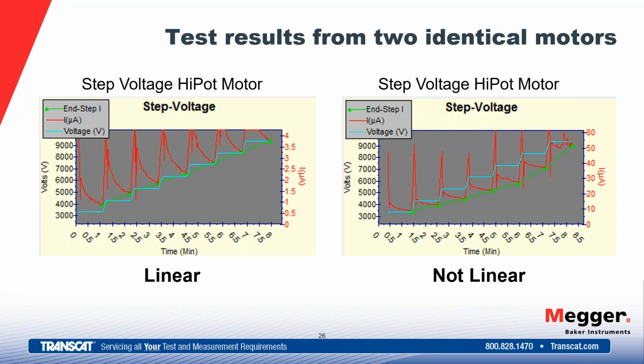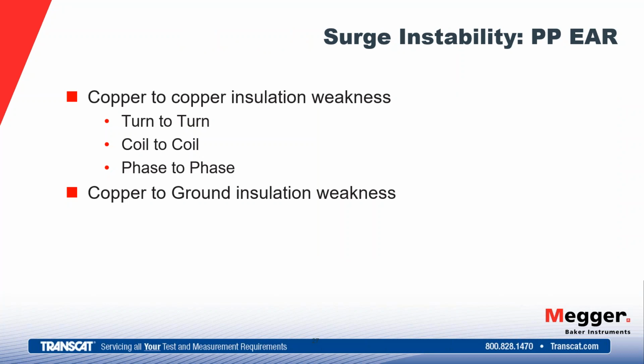So the step test allows you a little more control over when you stop the test or what you're reading there. You don't have to test to breakdown to have your information. You can see it here in this nonlinear response. Surge testing, again, we're looking for stability of this waveform as we pulse the motor under test. We get that turn to turn or coil to coil, phase to phase. We're looking at copper, possibly copper to ground insulations. If that happens on the early turns, we can see that with the surge test.